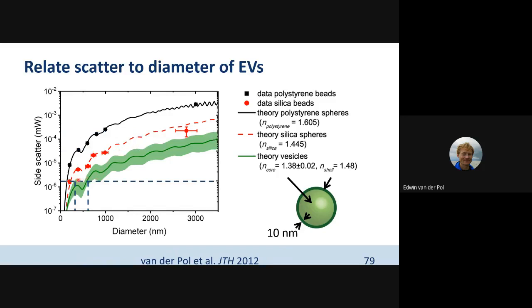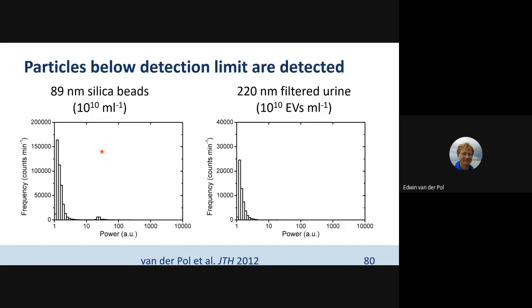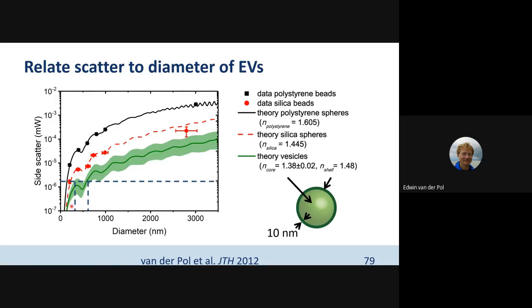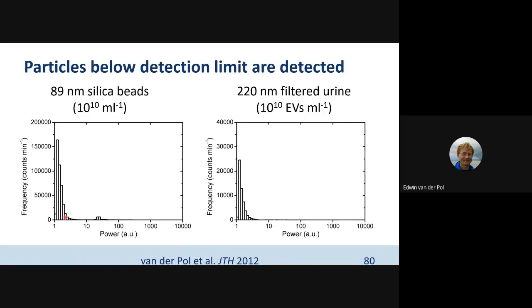Vesicles scatter light much less efficiently than polystyrene beads previously used to calibrate flow cytometers. We calibrated our flow cytometer with beads and Mie theory, then compared the previous gate of 500 and 900 nm polystyrene beads to vesicle diameters. If you apply that bead gate and call every particle within it a vesicle, that has nothing to do with measuring vesicles — you include particles of two micrometers and larger, which are cells. So a lot of research done that way was studying cells, not vesicles.